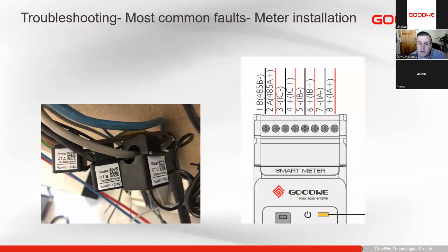Next, we look at the CT wiring. So the CTs all come pre-wired on our smart meters, but very often due to placement, the customer's utility board is full. You have to install an external board to put the smart meter in, although it's a nice only 2 DIN space. Very often you have to loosen the cables on top to route the wires through from the one board to the other board. Please pay careful attention to this wiring. As I said, we've never had a sticker incorrect, but if you swap the wiring around here, the sticker will be seen as incorrect because it is wired incorrectly.